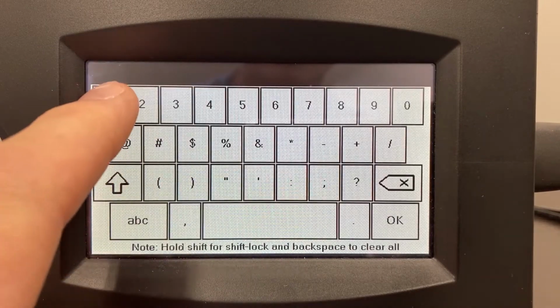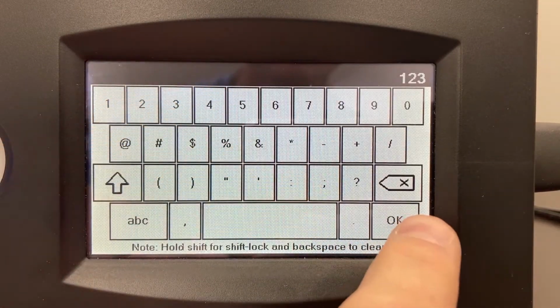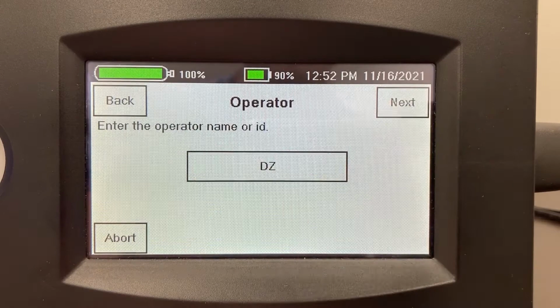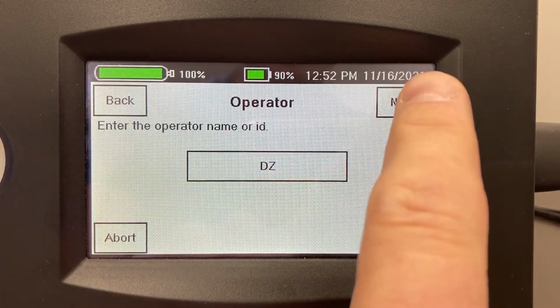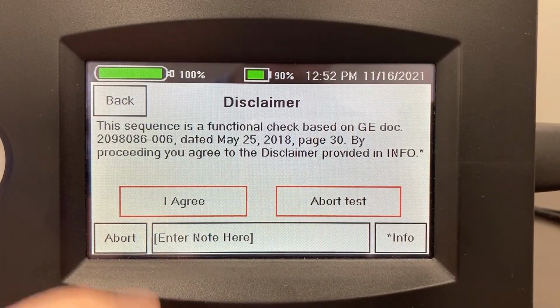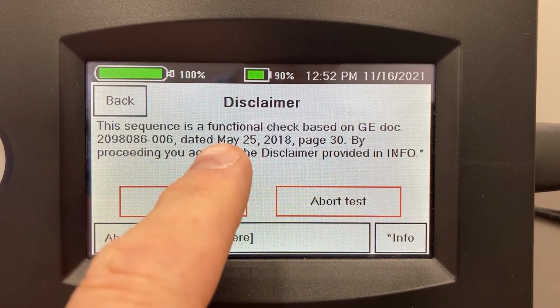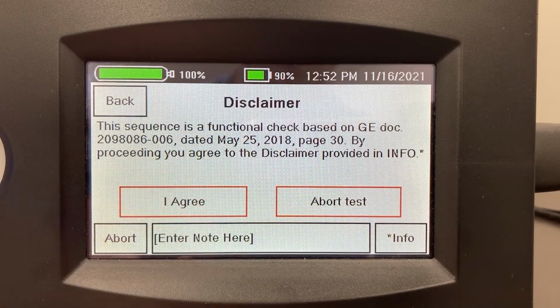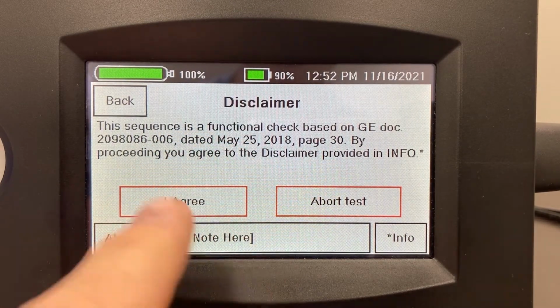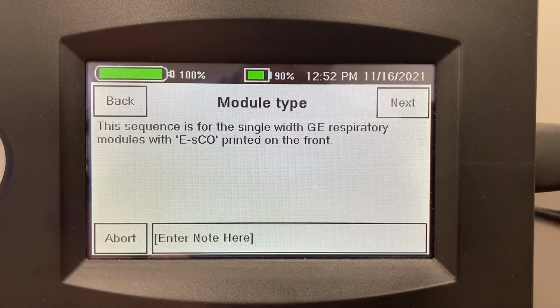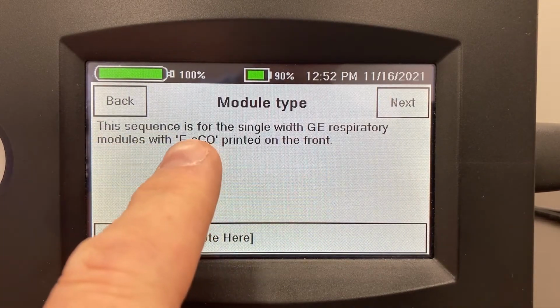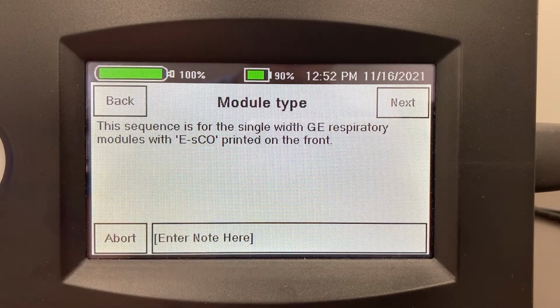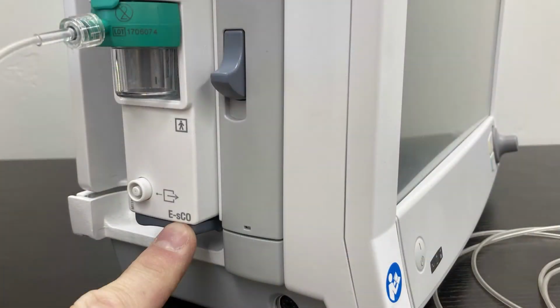I'm going to enter the ID of the device we're testing and our operator initials for the test report. This tells us what user manual or service manual the test sequence comes from. This just reminds us what module we're testing so we can make sure we have the right test sequence loaded.